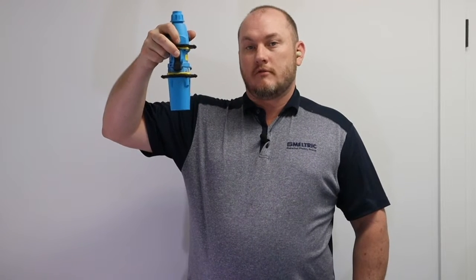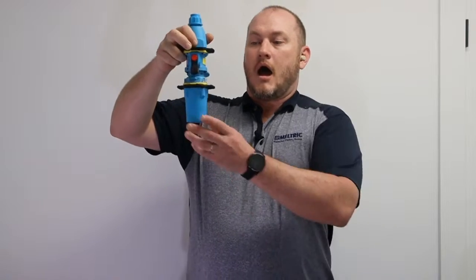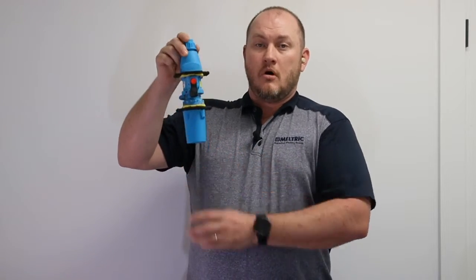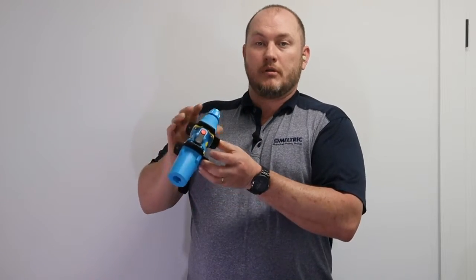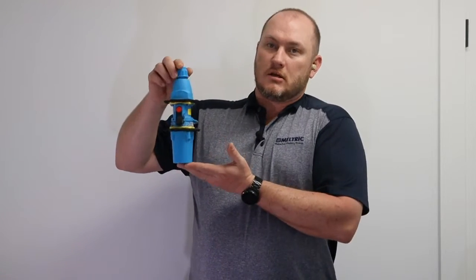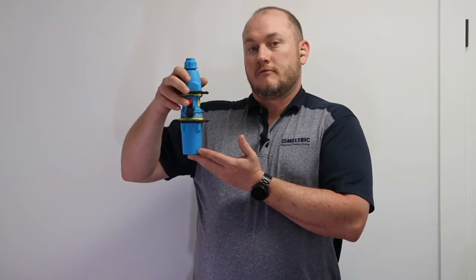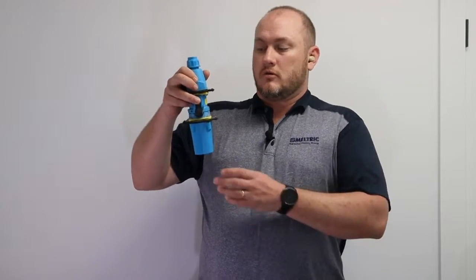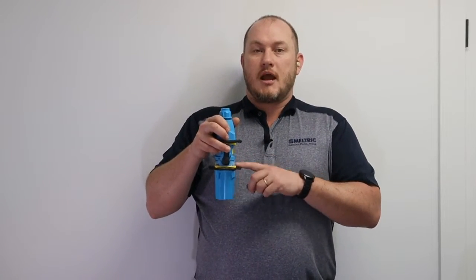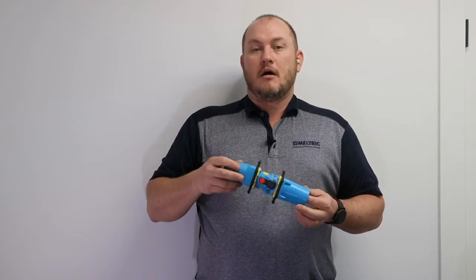So here's an example of Meltric's version of a switch-rated plug and receptacle. It's a DSN 20 amp, 120 volts. And what makes it a switch-rated plug is it has a switch integrated into the device. So when I press this button up here, I am able to separate the plug and receptacle while it's energized. I'm also able to make the plug and receptacle while it's energized. And that integrated switch function turns what would normally be considered a standard plug and receptacle or a pin and sleeve device into a switch rated plug and receptacle. So we're approved for operation as a switch. We comply with some of the details in National Electric Code as a switch.